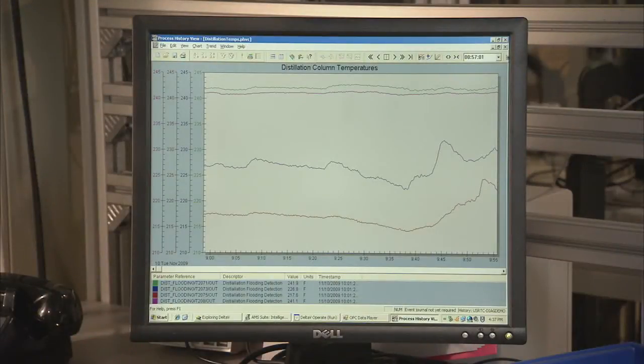Temperature measurements made across the packing have traditionally been used as a method to detect flooding. This chart here shows a temperature response under normal conditions in which there is clear separation in the column. The same response is seen just prior to flooding. Under flooding conditions, the packing bed temperatures will start to converge. However, this temperature convergence usually occurs well after flooding has taken place and does not provide an opportunity to take any preventative action.